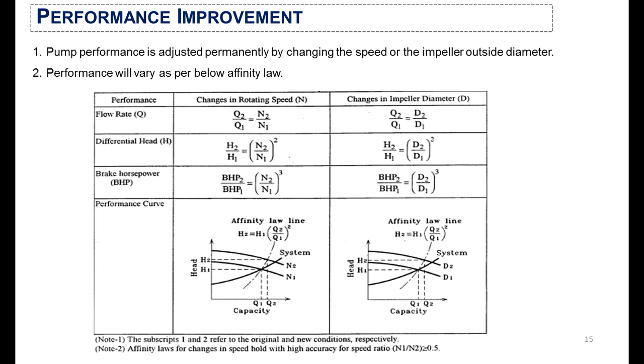On the other hand, you can also improve the performance of an original pump using the affinity law. The affinity law states the impact of impeller diameter and rotating speed of the pump on flow rate, differential head, and brake horsepower. Overall, we get the performance curve which defines the optimum point where the pump efficiency is highest.